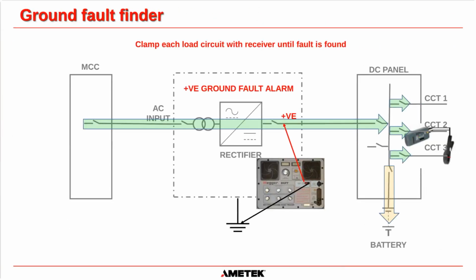And then we move the CT or the amp clamp down to circuit three, and you're going to see a reading on the receiver at this point, and it will say, hey, look, I found the signal that we're looking for. It will tell you that the fault is on circuit three, and you say, okay, now I've got to get the drawings out. I've got to find what circuit three feeds, and it's probably going to be an analyzer out in the field somewhere, and there may be water in the junction box of the analyzer, or there may be a junction box between circuit three and the analyzer, and that's got some water in it.